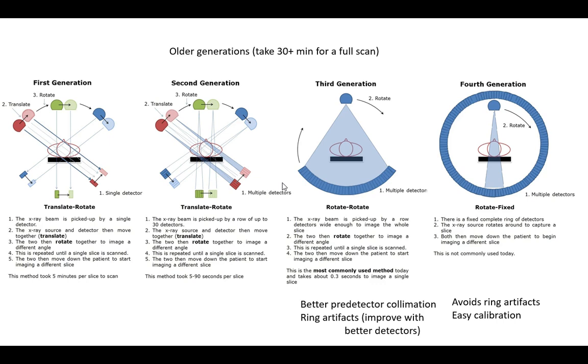So while it takes, let's say, 0.3 seconds, the braking, stopping the system rotating, reversing the rotation direction, and moving down took usually 8 or more seconds. This is why the later generations are going to try to avoid this problem. Because by the time this generation took over, your biggest slowdown, I mean, you're less than a second for the image, and then moving between slices, you're at say 8-10 seconds.